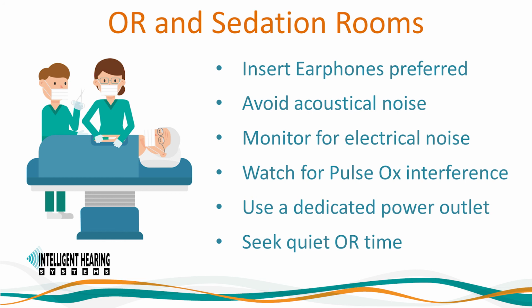problem in the future. If the pulse oximeter is plugged into mains power, use sockets away from those used for the ABR equipment. ABR equipment should always be connected to its own dedicated grounded outlet away from anesthesia machines and other machines that contribute to noise in the recordings. Try to negotiate carrying out testing at OR quiet times.